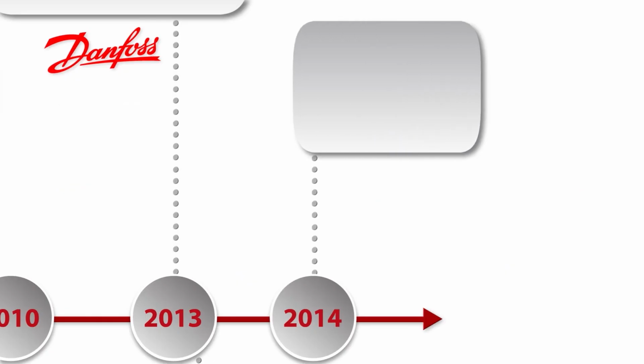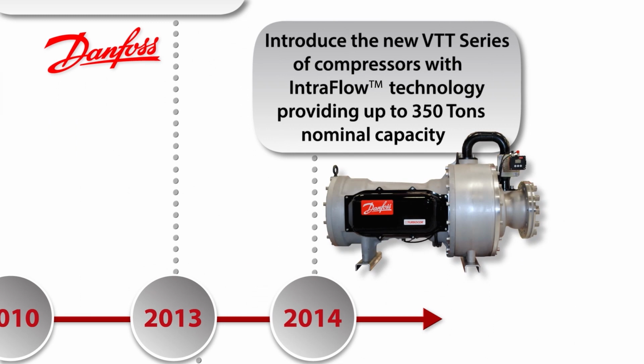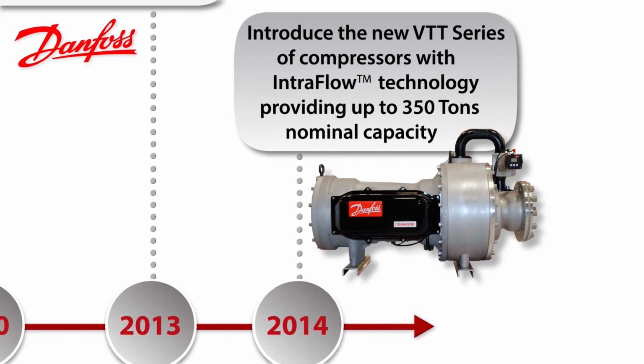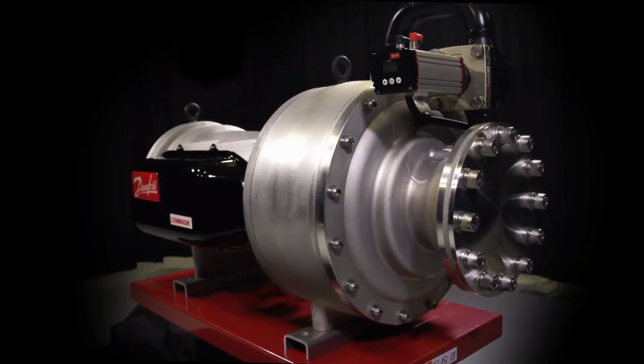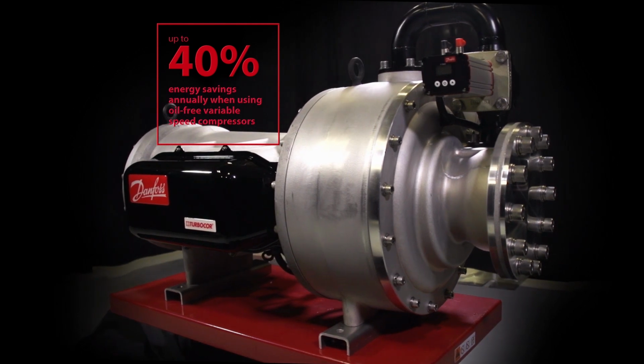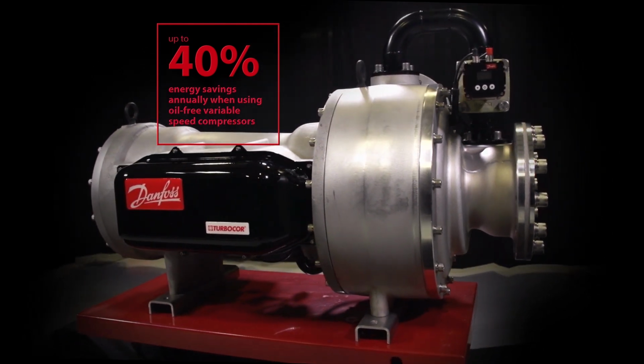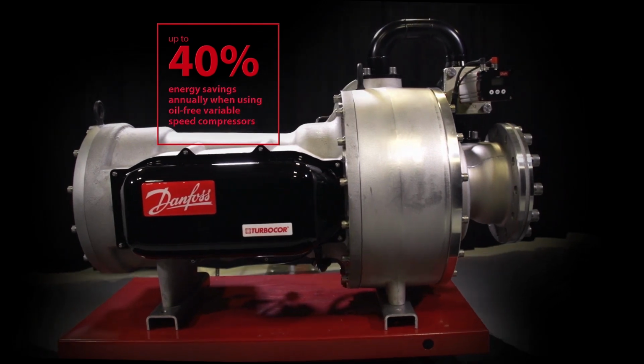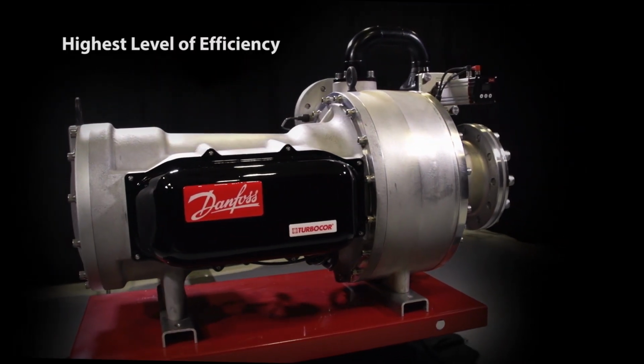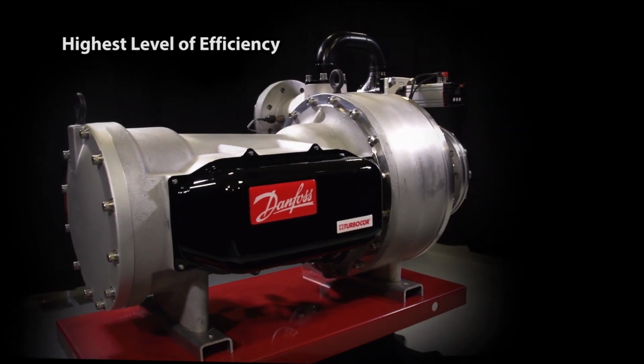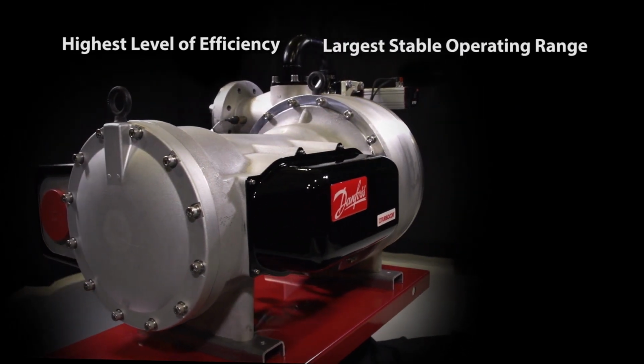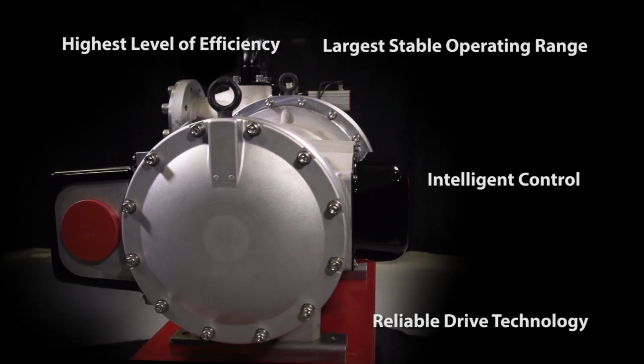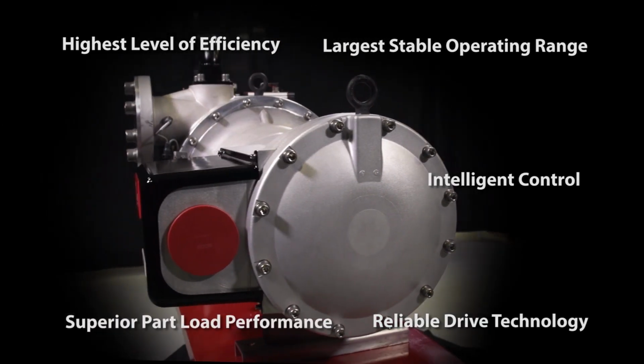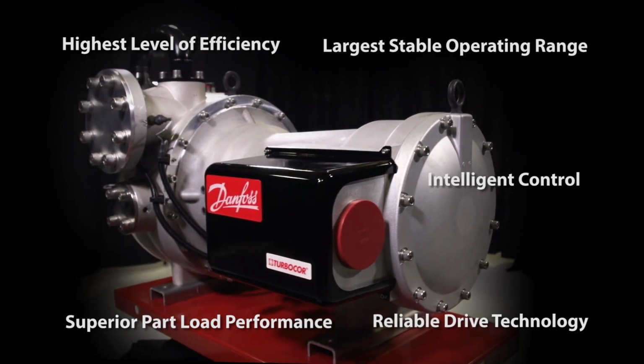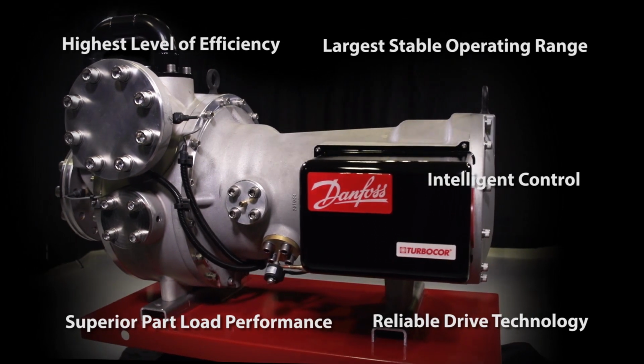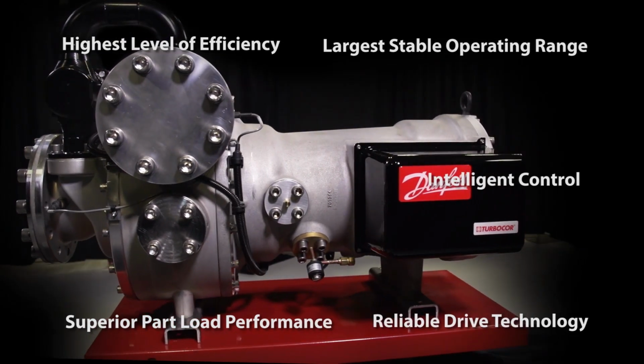Danfoss continues its history of innovation in the HVAC market with their introduction of the new Danfoss Turbocor VTT series of compressors with Intraflow technology. The VTT series compressors feature breakthrough technology that redefines the industry's expectations for stable operating range and associated performance of centrifugal compressors and chiller systems. As an oil-free, magnetic-bearing variable speed two-stage centrifugal compressor, the VTT series is designed to be the most efficient, reliable, quiet, and low-maintenance centrifugal compressor available. The VTT offers an economizer option and nominal capacity ranges from 200 to 350 tons.